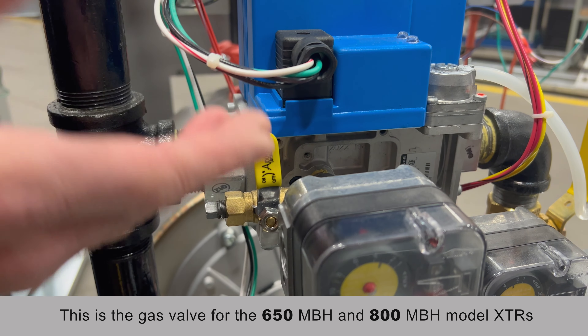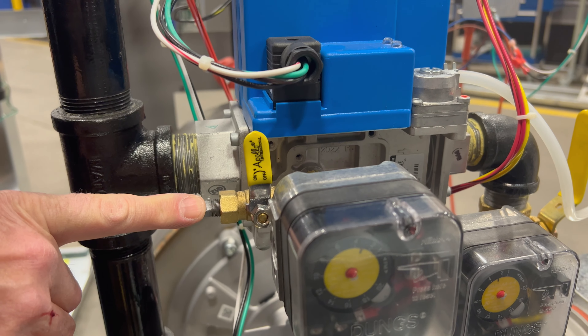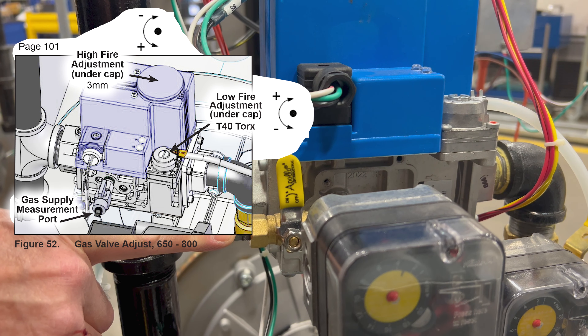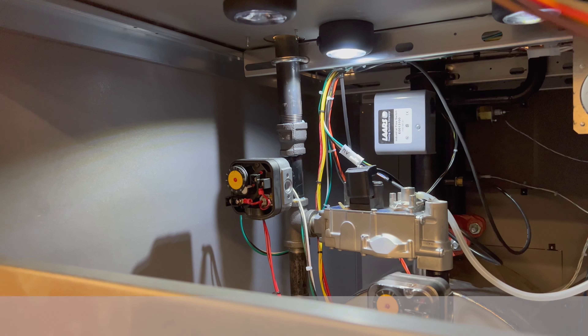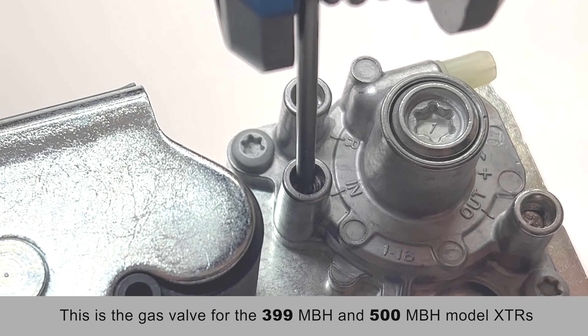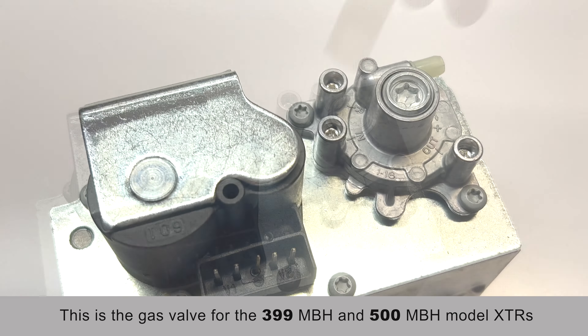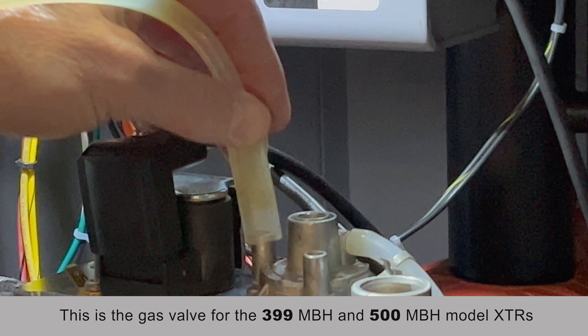On the Honeywell valve with CSD-1 boilers with high-low gas pressure switches, you can get your incoming gas pressure reading here. Incoming gas pressure is right here — it states IN. This is a number 9 Torx bit, and you would loosen that tap, hook up your hose, and get your incoming gas pressure reading.